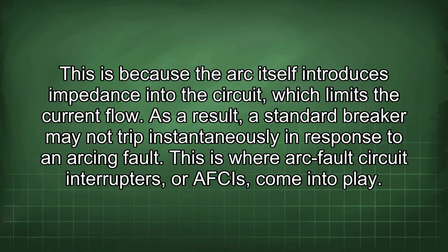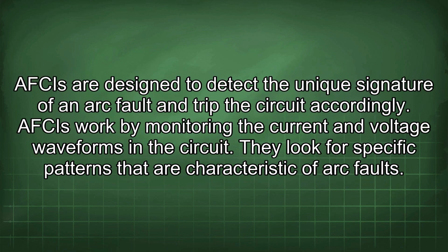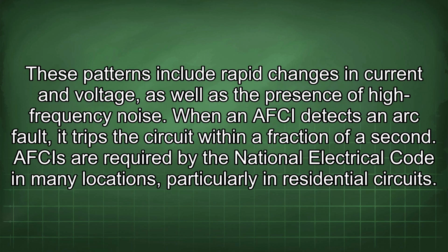This is where arc fault circuit interrupters, or AFCIs, come into play. AFCIs are designed to detect the unique signature of an arc fault and trip the circuit accordingly. AFCIs work by monitoring the current and voltage waveforms in the circuit. They look for specific patterns that are characteristic of arc faults. These patterns include rapid changes in current and voltage, as well as the presence of high-frequency noise. When an AFCI detects an arc fault, it trips the circuit within a fraction of a second.